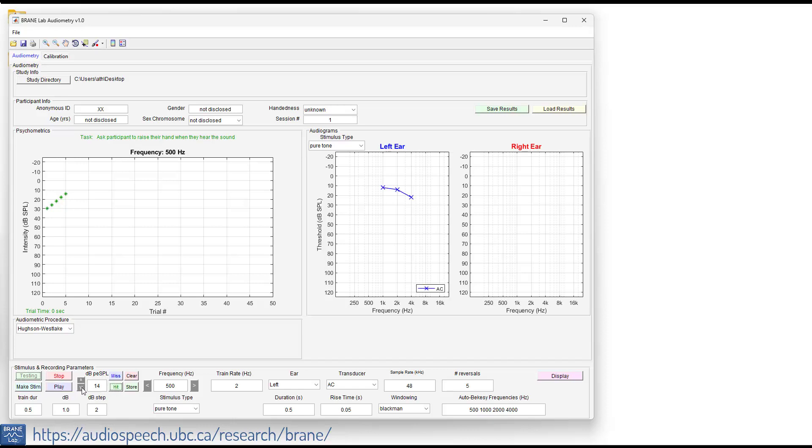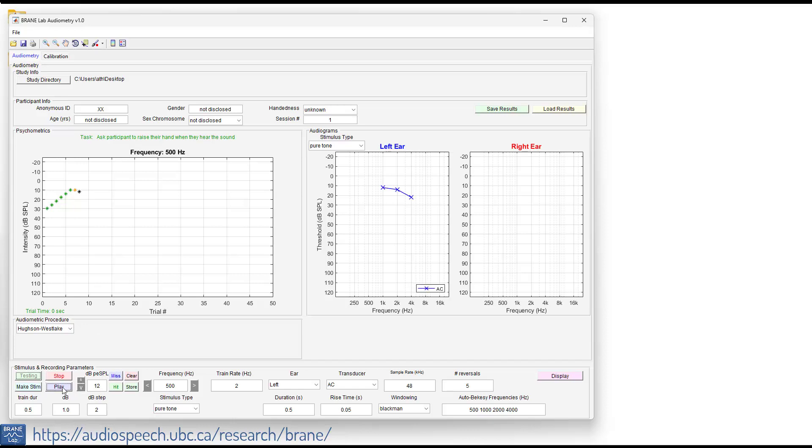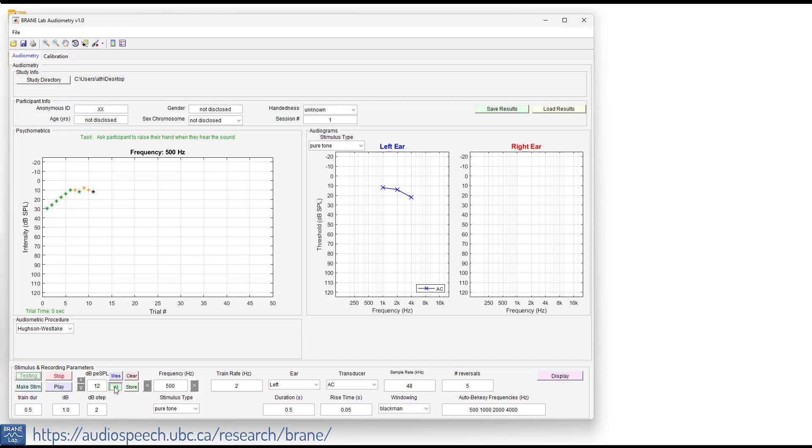Now you can put in foils here if you're doing standard audiometry practices. I'm the presenter and the participant, so I know when things are happening. I was just talking there and forgot where I was. We're at 10. I did not actually hear that, so that's actually a miss there. Got to go up. Heard that. Okay, so 2 on the ascending and we'll click on store and then stop.